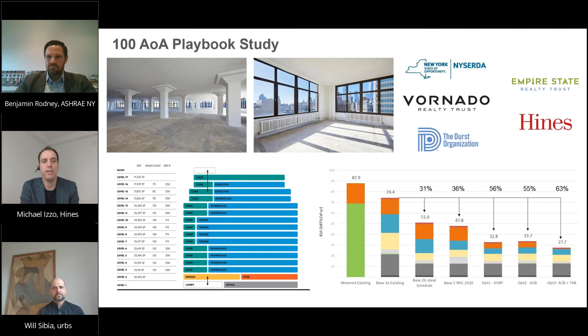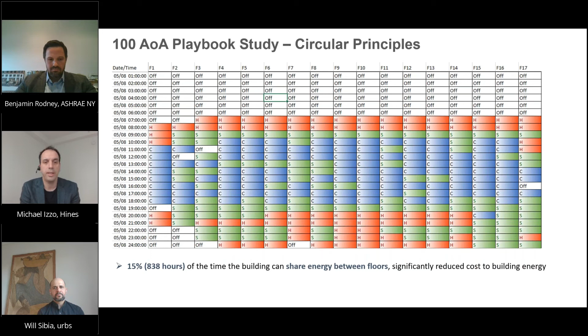We looked at many different strategies, and all of them came in at 30 to 60% of what the status quo would be. That's because we took it as a whole aggregate—each floor, each exposure, each occupancy has a different utilization across the day, the year, the month. By connecting all those floors in order to harness that wasted energy, we found that 15% of the time we could actually shut our energy systems off and just share energy between floors, significantly reducing energy use across the whole building.